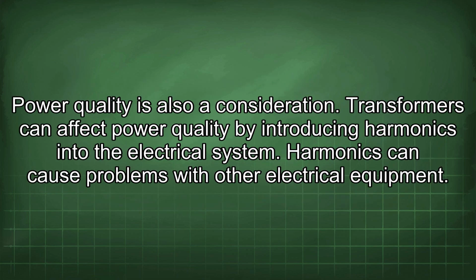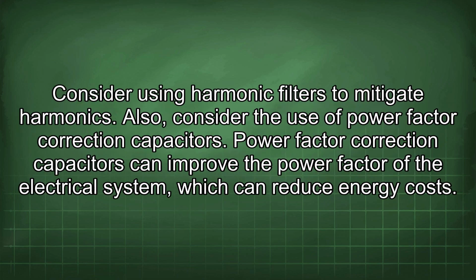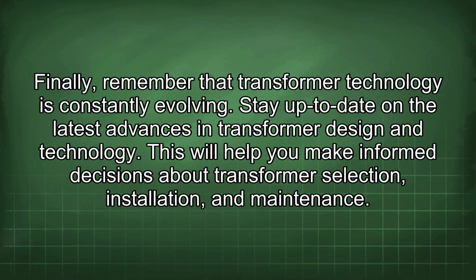Power quality is also a consideration. Transformers can affect power quality by introducing harmonics into the electrical system. Harmonics can cause problems with other electrical equipment. Consider using harmonic filters to mitigate harmonics. Also, consider the use of power factor correction capacitors. Power factor correction capacitors can improve the power factor of the electrical system, which can reduce energy costs. Finally, remember that transformer technology is constantly evolving. Stay up to date on the latest advances in transformer design and technology. This will help you make informed decisions about transformer selection, installation, and maintenance.